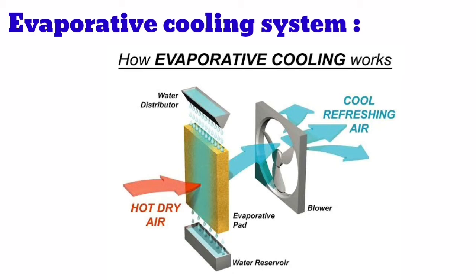As the hot dry air passes over the wet absorbent pad, some of the water evaporates. This cools the air in the same way moisture evaporating from your skin cools your body. The air leaves the cooler at a reduced temperature, which is dependent on the relative humidity of the air being drawn into the cooler.